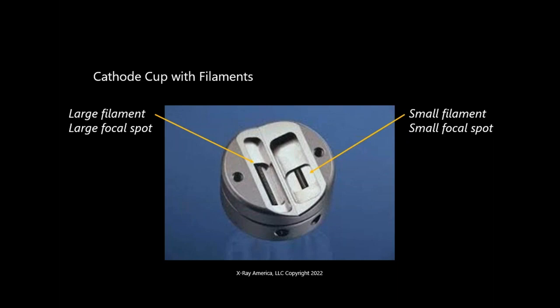Well, it could be the generator, but all things being equal, we know they didn't change the generators in the room, we know they changed the tubes. It's like the AMX 4s, I can tell the difference on my radiation meter between a unit that was made in China and the older units. And the older units had a better kV waveform. It's what's made up in the filaments and the emissions, right?